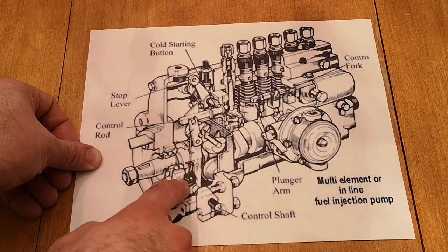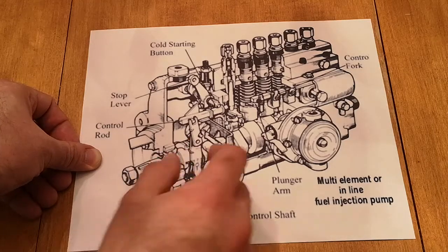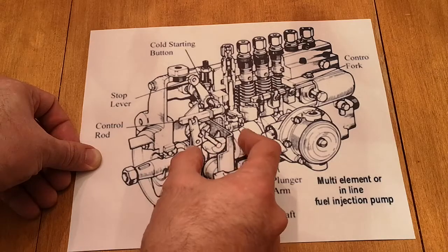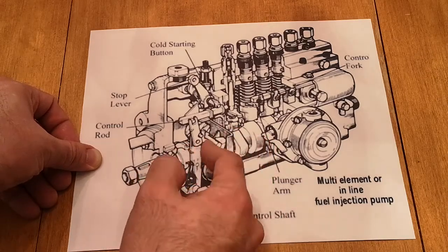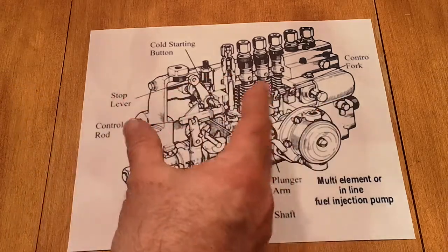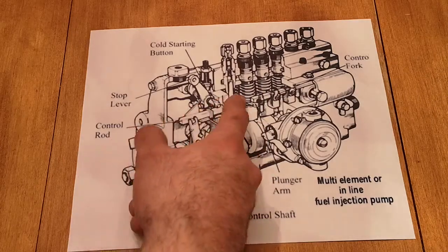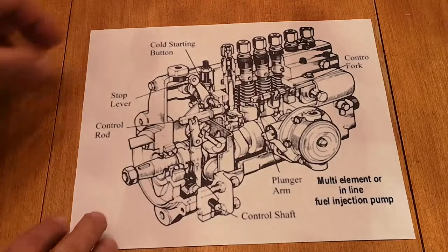The governor contains weights, which spin around, and then there's also a spring over here that constantly pushes against the weights. The two of them combined will control the control rod, which controls the amount of fuel going in.